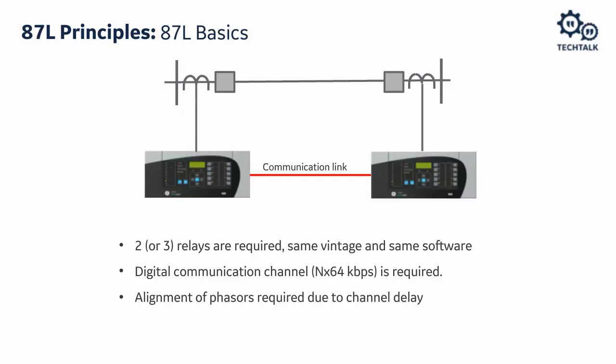The relays have to be the same vintage and same software. You cannot have one relay from one vendor and another from a different vendor, or one relay of an older generation and another of a newer generation. We also need a digital communication channel, which we call N times 64 kilobits per second.